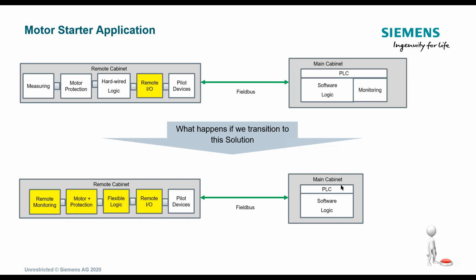to the PLC. What this gives you is that the logic becomes simpler in the controller, and the controller is now turning more into a traffic cop, or monitoring alarms. And if it has an alarm at a pump, then it says, okay, this remote cabinet says I have an alarm, we have a problem with this pump. Then the controller says, okay, with this pump we have a problem, I need this valve shut, and I want to turn on a parallel system and open up this valve and turn this pump on. So this becomes an alarm handler, or a product handler for it.